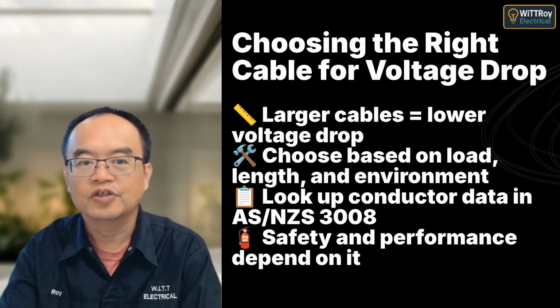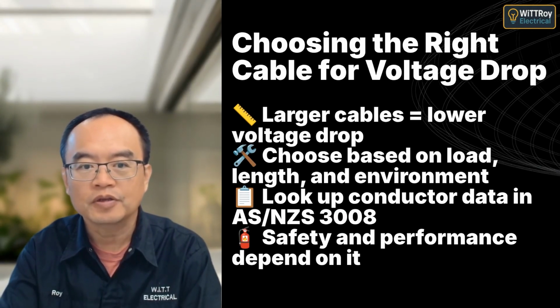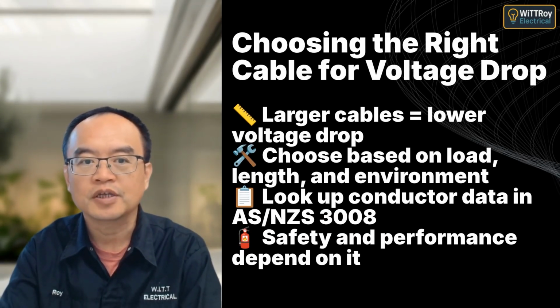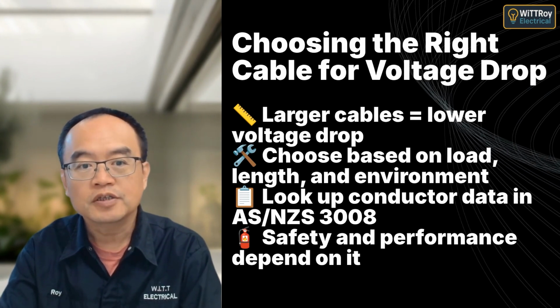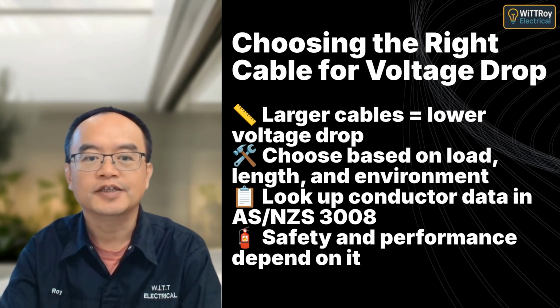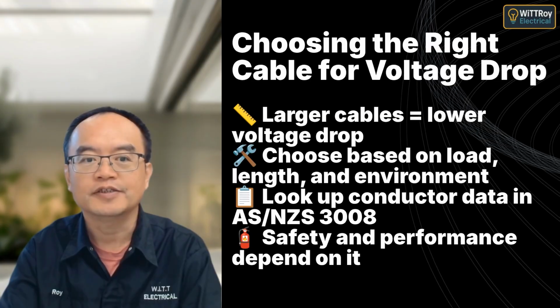To reduce voltage drop, you may need to upsize the cable. Always balance the load, length, and conditions when choosing a conductor, and double check with AS/NZS 3008 to stay compliant.